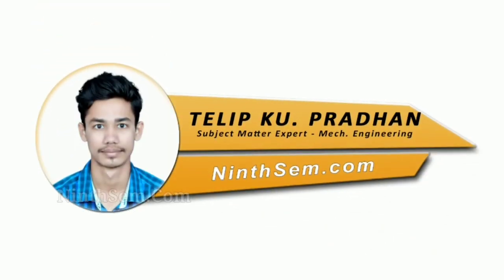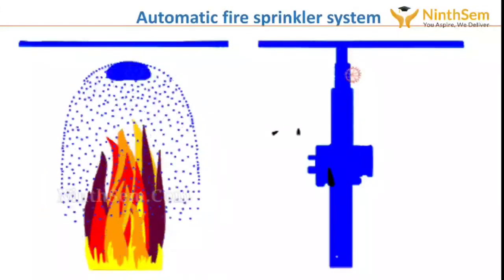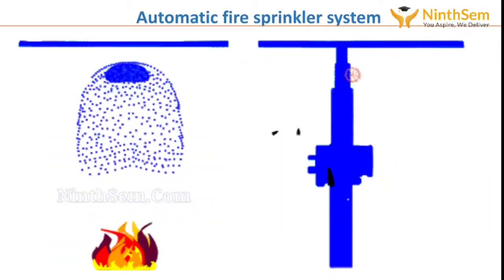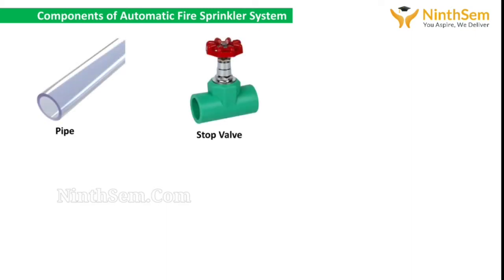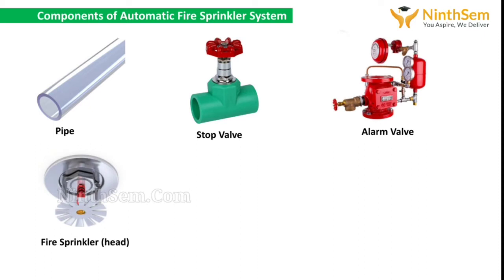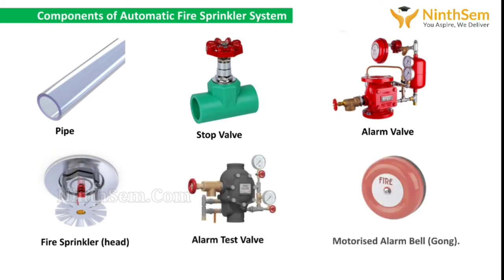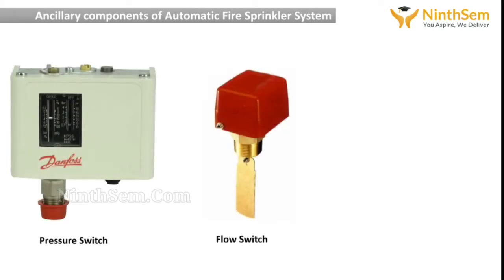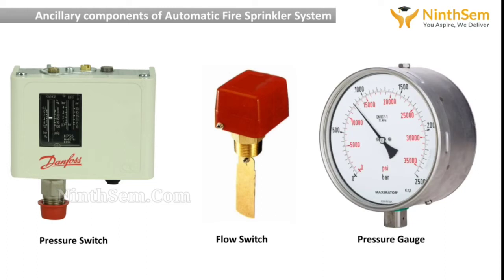In this video, we are going to discuss an automatic fire sprinkler system. An automatic fire sprinkler system typically comprises a series of individual components including pipe, stop valve, alarm valve, fire sprinkler head, alarm test valve, and motorized alarm bell, which is also called gong. In addition to this, there are additional components that support this arrangement, including a valve monitor, pressure switch, and flow switch. Let's discuss the purpose of each component.